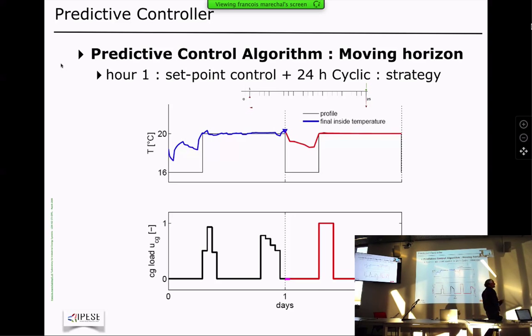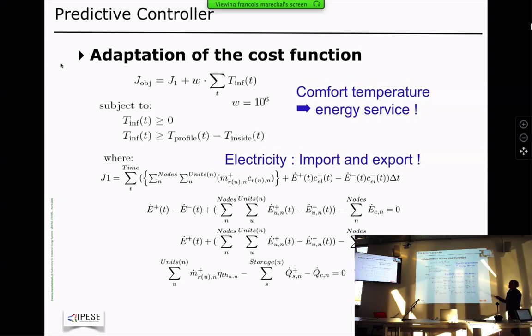In order to do this, we had to adapt the optimal predictive control model used in the design phase. The first adaptation was to add a penalty if the temperature goes below the set point. Otherwise, since the system tries to operate at minimum cost, the cheapest way to satisfy the heat load would be to let the temperature go down. No heat, no cost. So even with a perfect prediction of the set point, we have to add a penalty to be sure we won't disturb comfort.